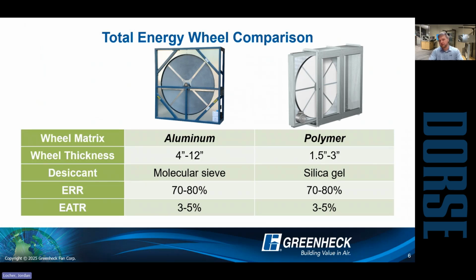So two technologies, right? You got wheels and cores. The most common types of wheels that you'll see in the industry are aluminum wheels and polymer wheels. For Greenheck, we exclusively deal with polymer wheels on our standalone energy recovery. Big difference between the two, they're both very, very effective, right? So wheels are the most effective technology out there. However, there's a difference in the thickness of the media to accomplish that, right? So generally speaking, aluminum wheels are much thicker than polymer. So you can see that 4 to 12-inch range, whereas our polymer wheels come in a standard 1.5 to 3-inch size. From an enthalpy recovery point of view, 70 to 80% can be expected.